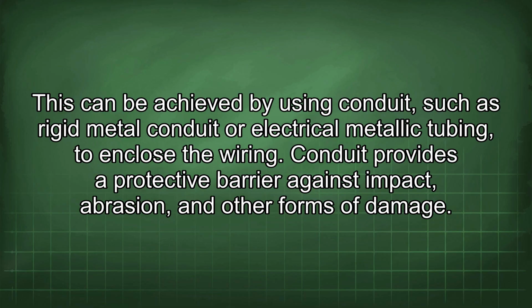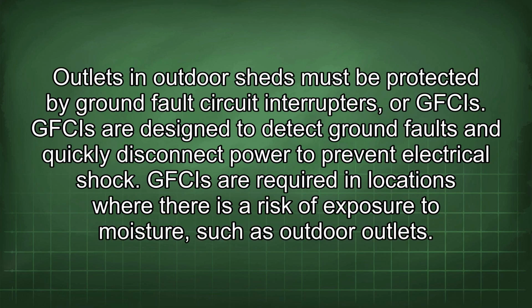This can be achieved by using conduit, such as rigid metal conduit or electrical metallic tubing, to enclose the wiring. Conduit provides a protective barrier against impact, abrasion, and other forms of damage. Outlets in outdoor sheds must be protected by ground fault circuit interrupters, or GFCIs. GFCIs are designed to detect ground faults and quickly disconnect power to prevent electrical shock. GFCIs are required in locations where there is a risk of exposure to moisture, such as outdoor outlets.